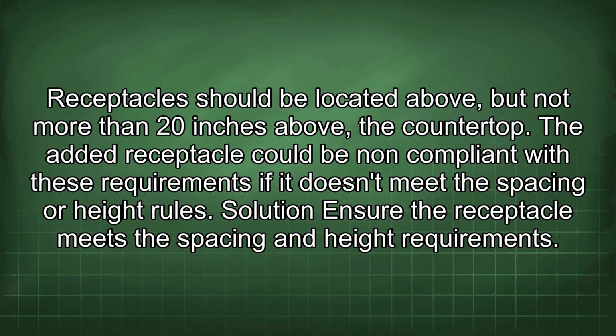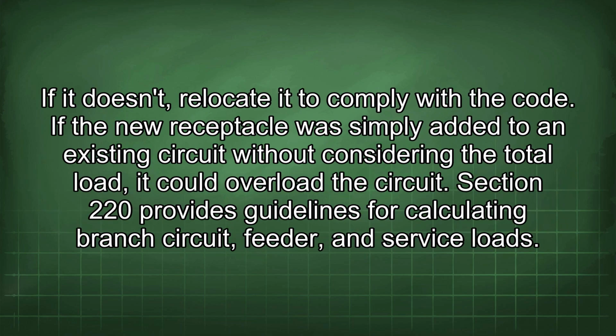Receptacles should be located above, but not more than 20 inches above, the countertop. The added receptacle could be non-compliant with these requirements if it doesn't meet the spacing or height rules. Solution: ensure the receptacle meets the spacing and height requirements. If it doesn't, relocate it to comply with the code. If the new receptacle was simply added to an existing circuit without considering the total load, it could overload the circuit.